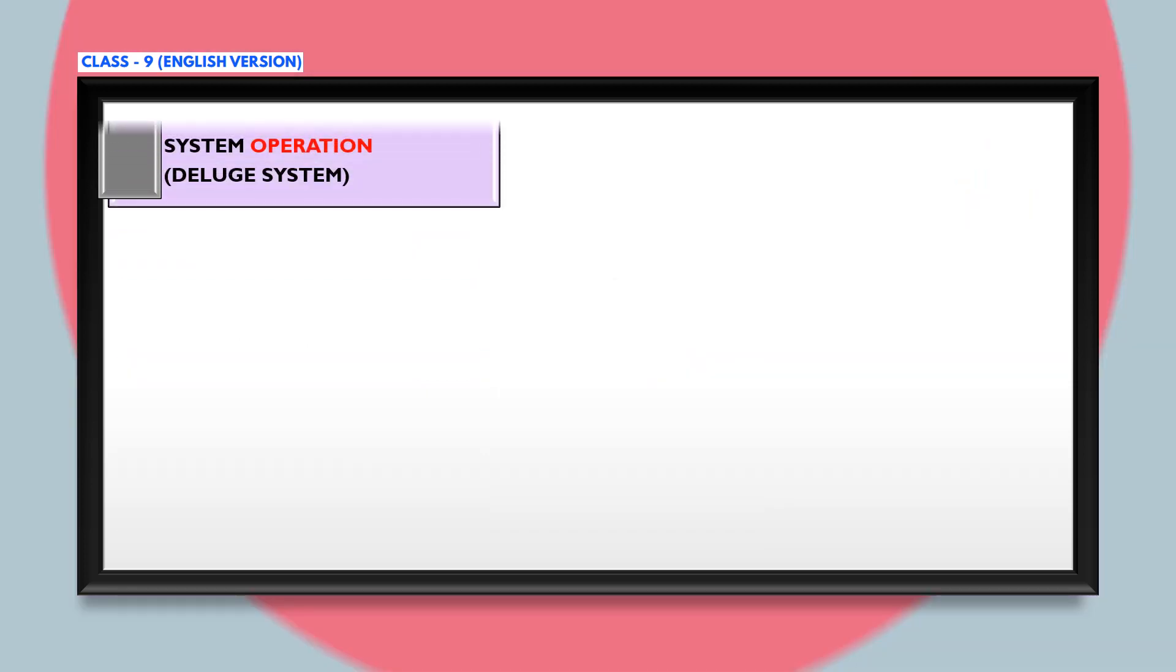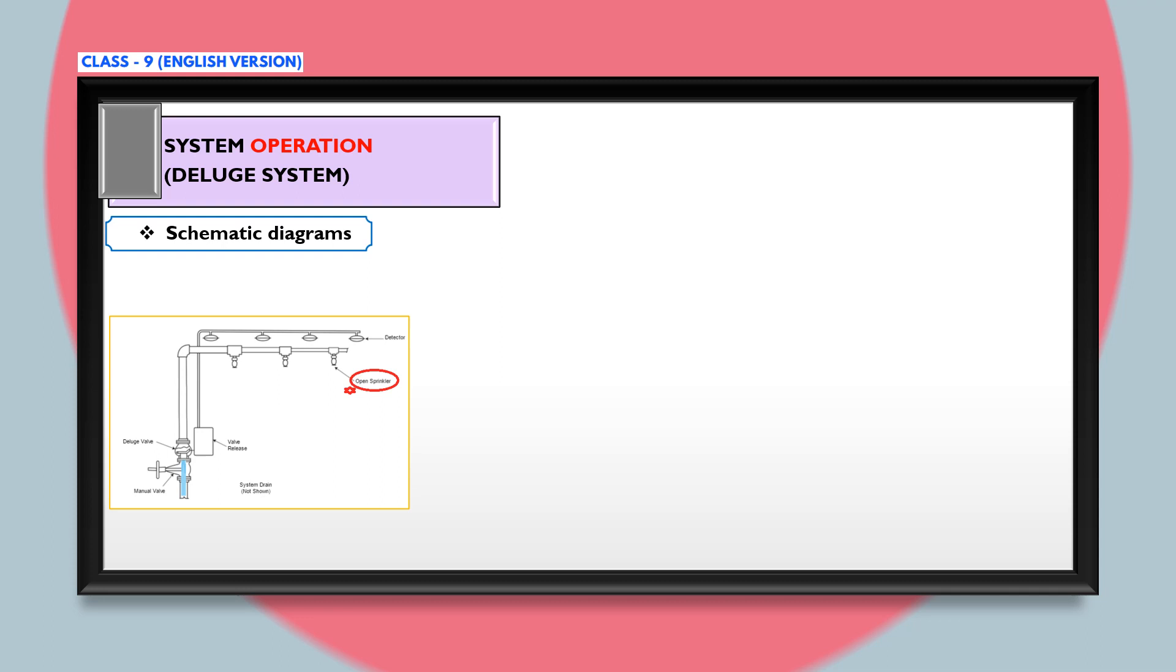Now let us understand the system operation of this deluge type in detail. As you can see on your screen, a schematic diagram shows that the water is filled till the deluge valve. A supplemental detection system with a releasing panel is installed in the same area as the open sprinklers. All sprinklers or nozzles are installed which are of open type, and there is no water in the piping above the deluge valve.